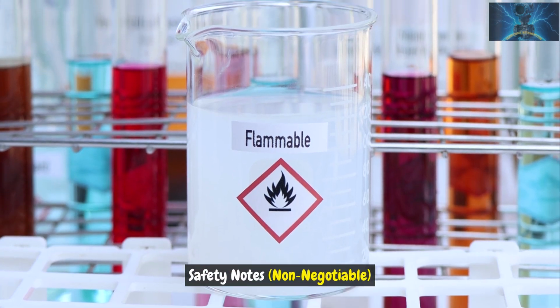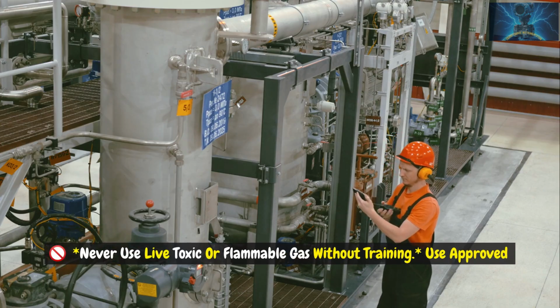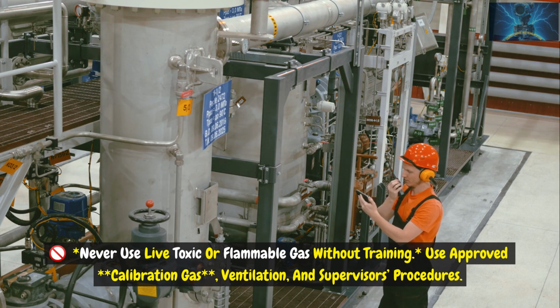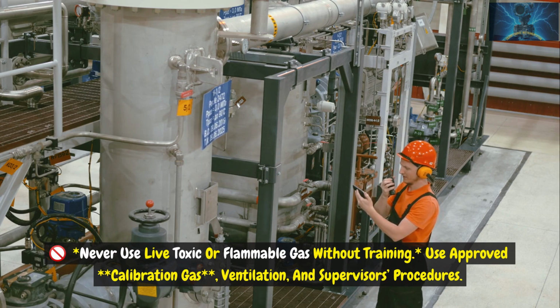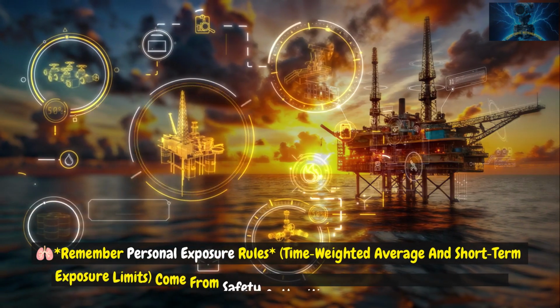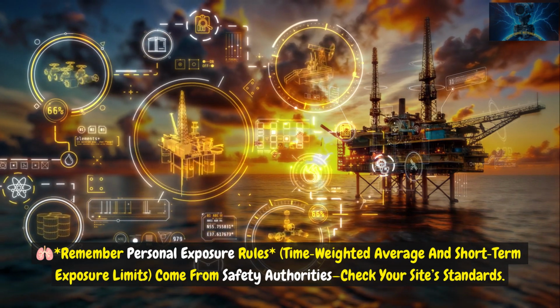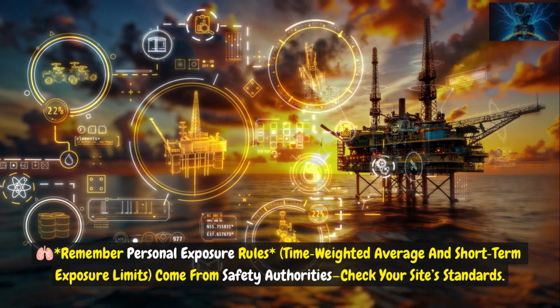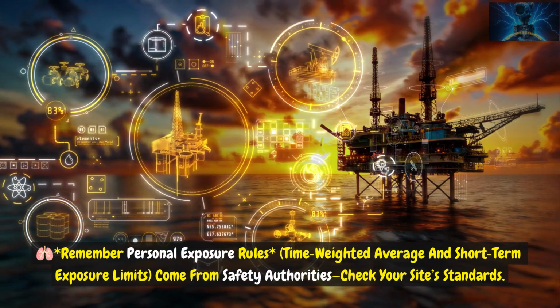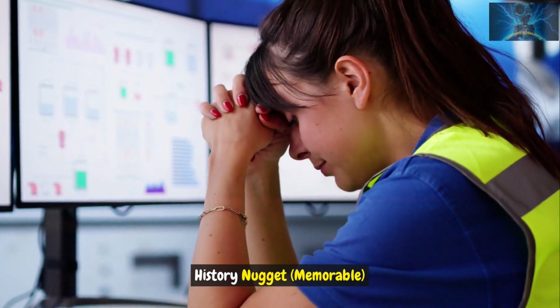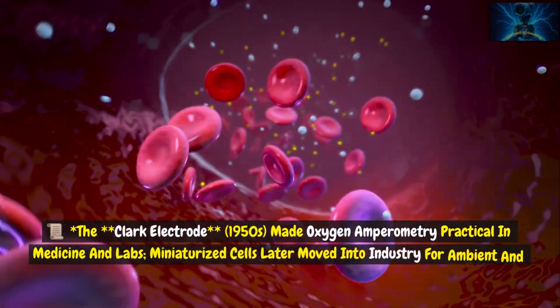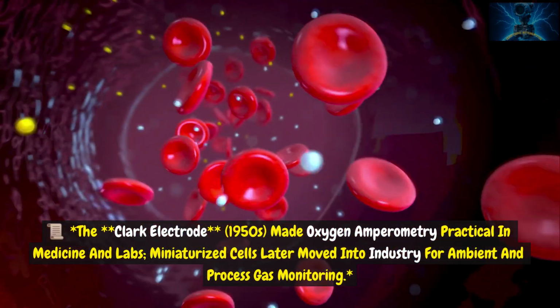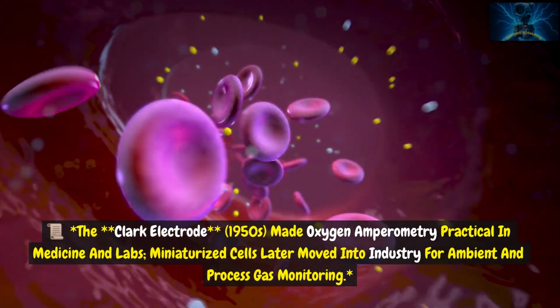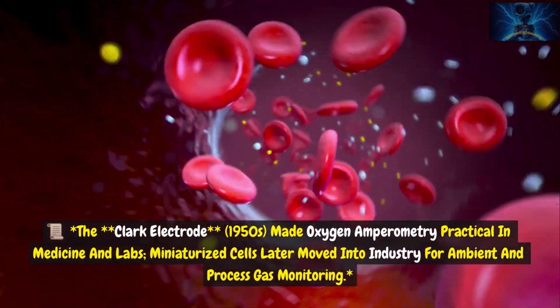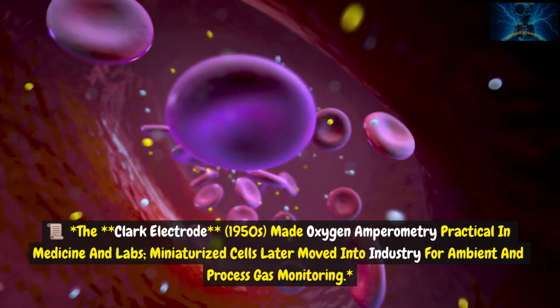Safety notes, non-negotiable. Never use live toxic or flammable gas without training. Use approved calibration gas, ventilation, and supervisor's procedures. Remember personal exposure rules, time-weighted average and short-term exposure limits. They come from safety authorities. Check your site's standards. History nugget, memorable. The Clark electrode, 1950s, made oxygen amperometry practical in medicine and labs. Miniaturized cells later moved into industry for ambient and process gas monitoring.